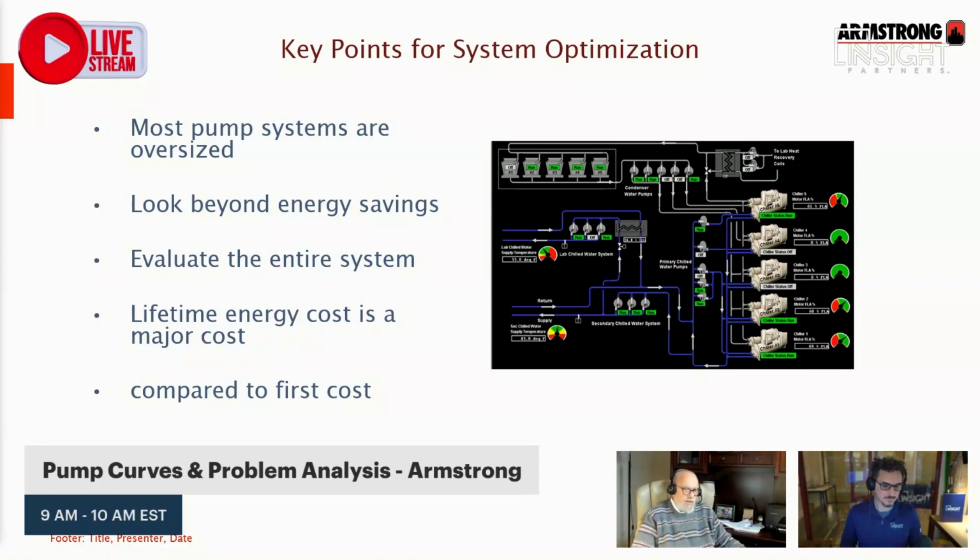They understand some of the information that's being presented. But when we move into variable speed pump curves and optimized pump selections, a lot of engineers and contractors and TAB contractors don't understand. They really got to pay attention to the data that's on the curve, because I've had a couple of jobs here recently where they've come back and said, "Oh no, you built the pumps wrong. They have the wrong impellers in them.